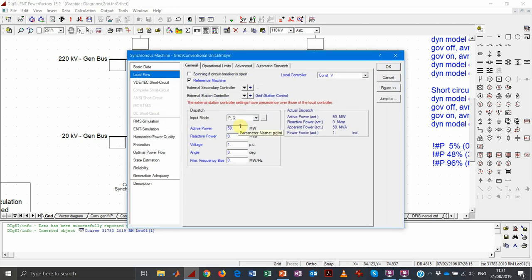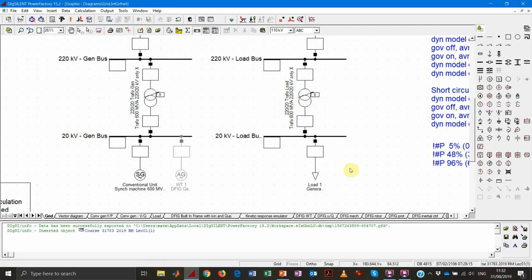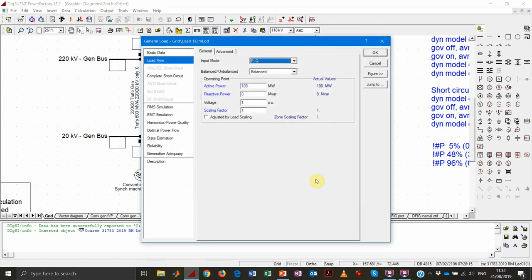Keep in mind that since we have just one generator in the system, it doesn't matter what the dispatched active power is, because PowerFactory will override any set point we enter — it needs to use the generator to balance all active and reactive power in the system. The load has been dispatched with a consumption of 100 megawatts of active power and no reactive power.